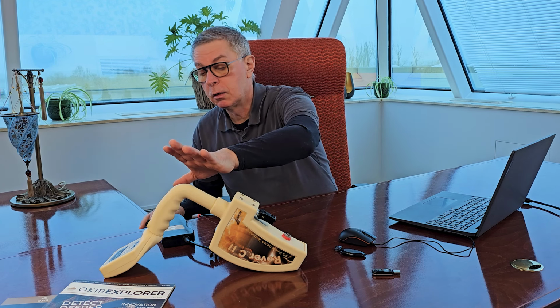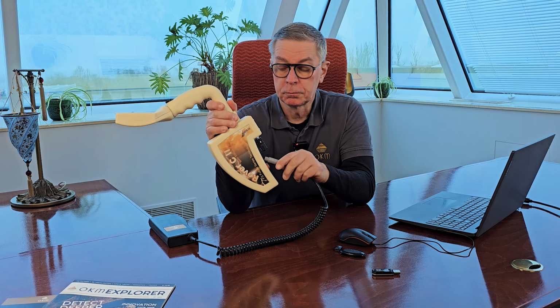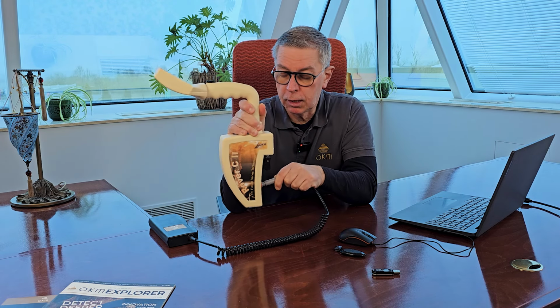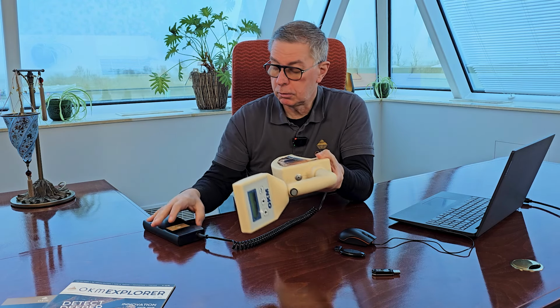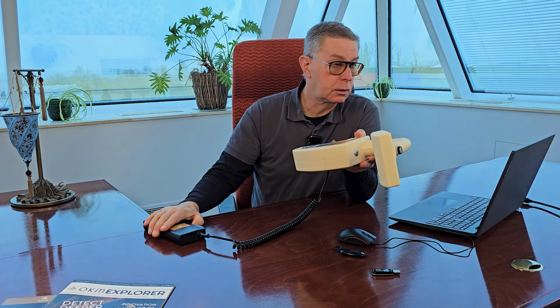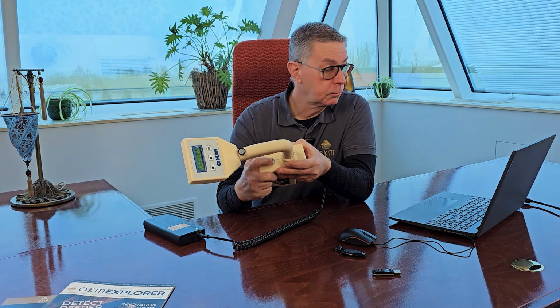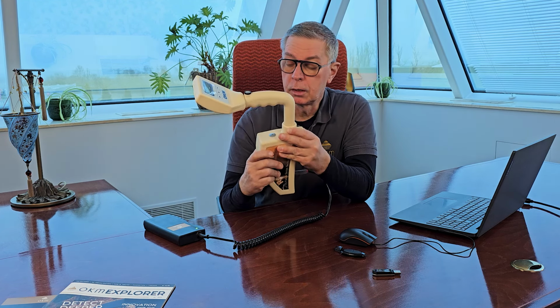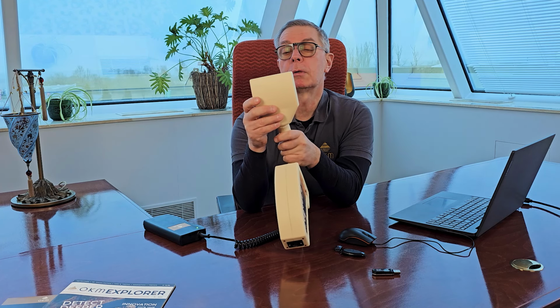in. On the Rover C2, I am now going to plug it in. You could have had this already in advance, but at this point it's very simple. Plug in the power, take the power pack, turn it on. I'm going to turn on the Rover C2, and I have a green light. It is on in our display window. It comes up here, it says background light automatic. I'm going to click OK.